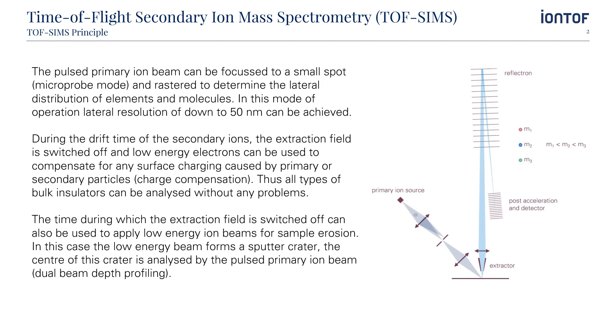The pulsed primary ion beam can be focused to a small spot — microprobe mode — and rastered to determine the lateral distribution of elements and molecules. In this mode of operation, lateral resolutions of down to 50 nm can be achieved.